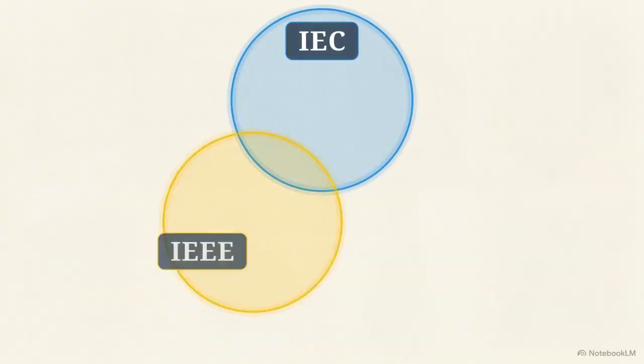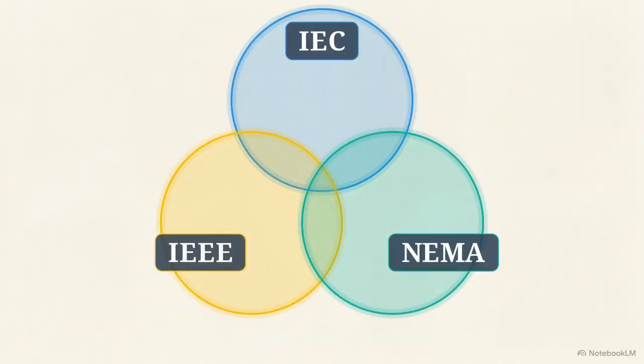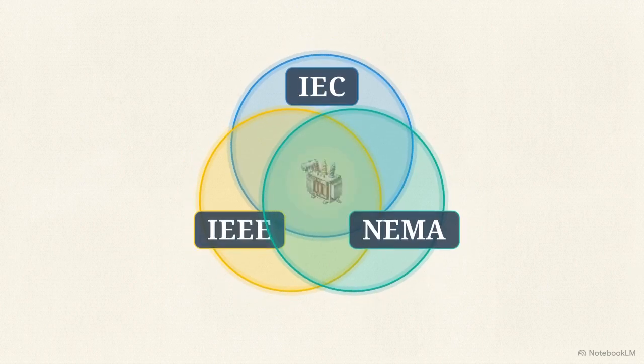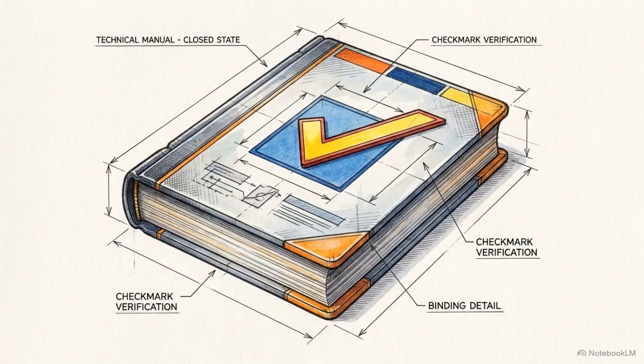Commissioning these transformers requires strict adherence to multiple engineering frameworks, including IEC, IEEE, and NEMA standards. When these codes conflict on a specific tolerance, the governance rule is absolute. The technician must apply the most stringent approved requirement.